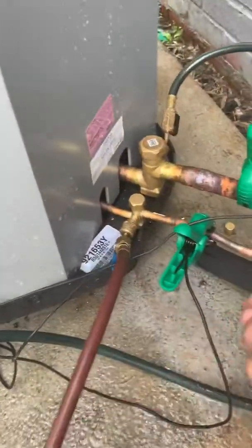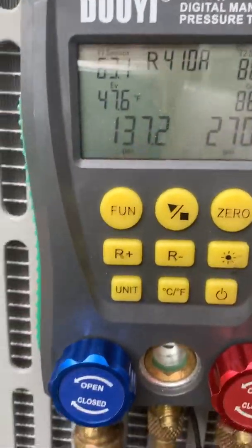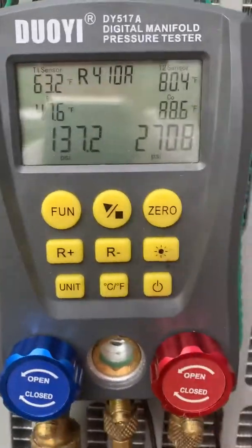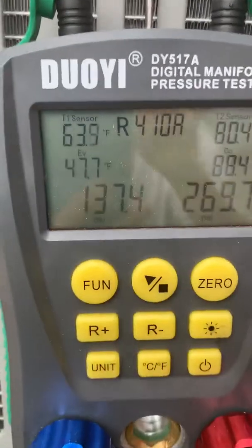If you pay attention right here, this red thing is your liquid line. Your liquid line is always your small line; your vapor line or low side is always going to be your big line. Now I've got a digital gauge here - a little Duoyi - seems to work great. These here are your liquid line side, red. I've got a thermal probe that goes in there. I'm looking at this number here and this number here. This is my evaporator temperature upstairs in the attic, and this is my condenser temperature right outside this unit. My evaporator temperature is 47.6, and my line on that side is reading 63.7.